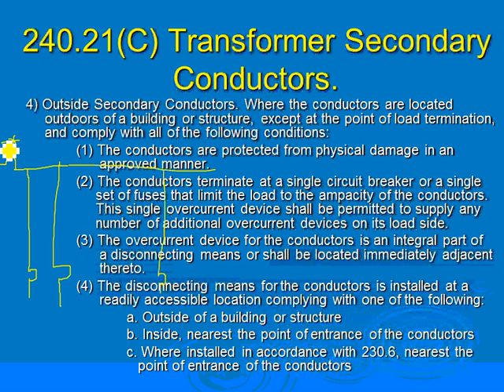I can have number 14 here with 15 amps. I'm limiting the load to 15 amps with number 14, no problem, and I'm outdoor. If I have a short circuit in a number 14, I would make sure that the circuit breaker will trip fast enough before number 14 melts. How do you do that?